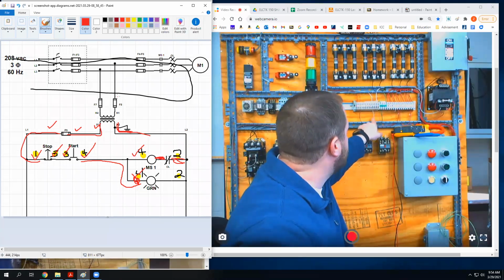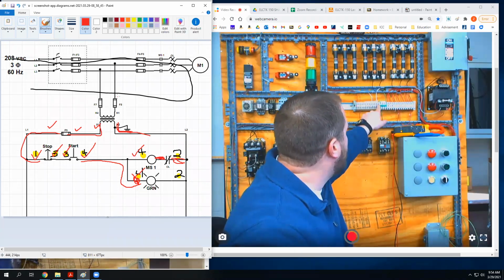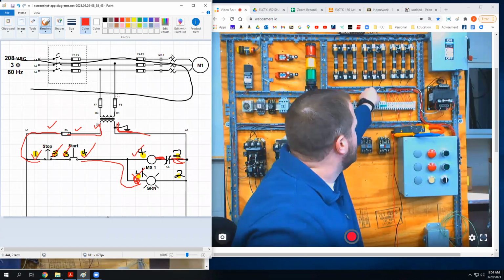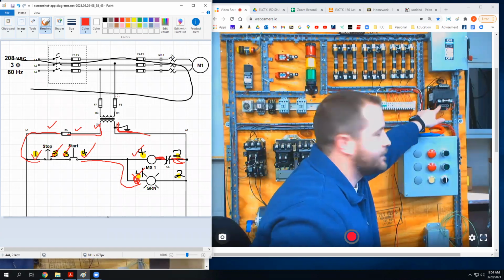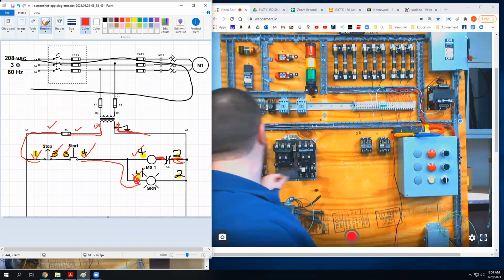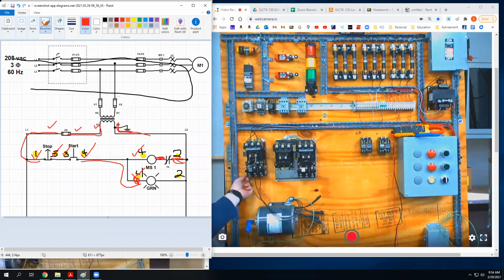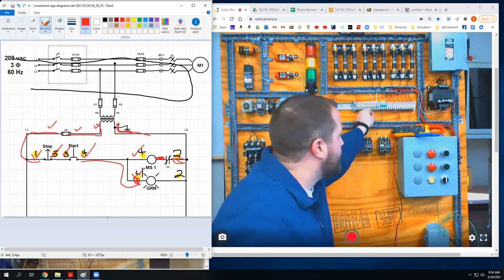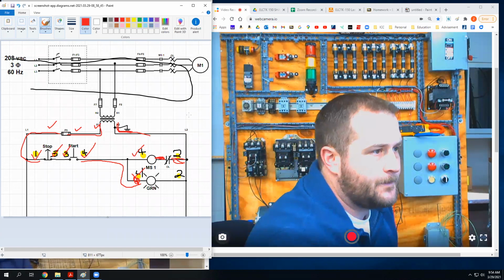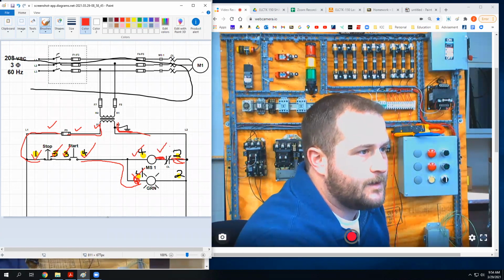So I could land a 2 or a white wire anywhere on here, and it would be joined to this white wire going back to the transformer. Which means that this wire on the bottom of my normally closed overload contact needs to come up and land right here, and it's already done. So that means this is done and this is done.